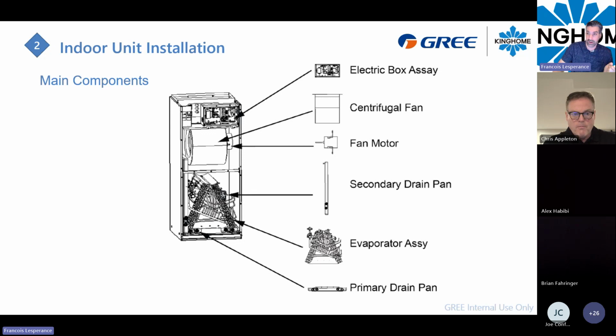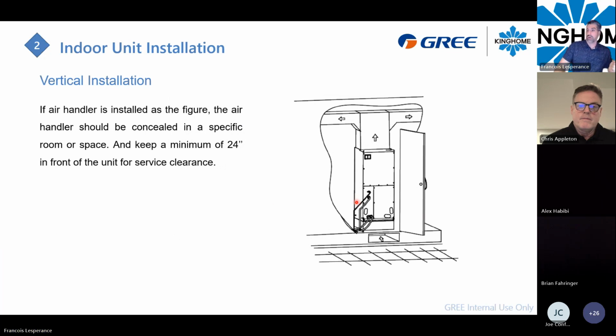So what's inside this air handler? You will have your electrical box assembly, your blower motor, and inside of it the A-coil with 2 drain pans: the primary drain pan here and a secondary drain pan if you change the orientation of this air handler. Around the unit, you can have as little as 1 inch all around, but in front of the unit we suggest a minimum of 24 inches clearance for service and for connecting the piping and the power. So 2 feet away from the front door of this air handler is a good thing to have.